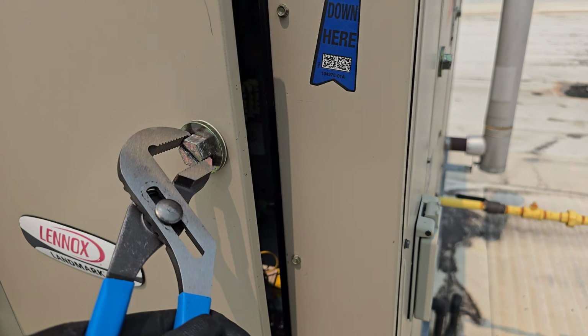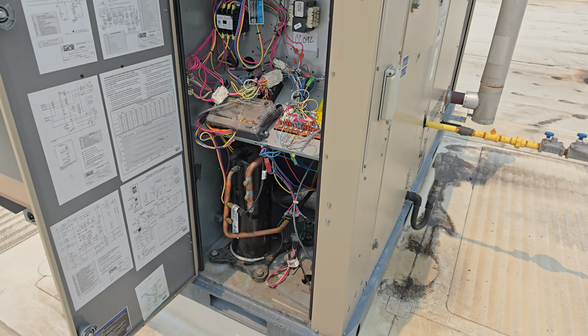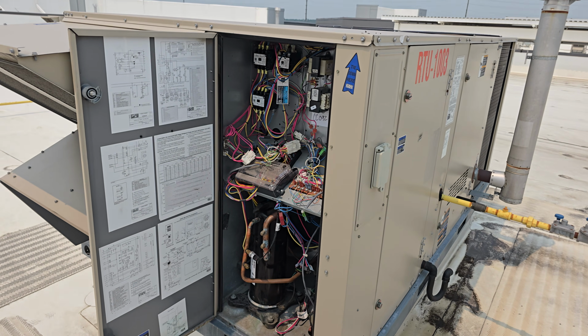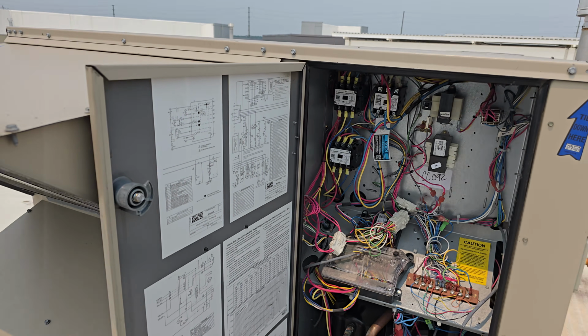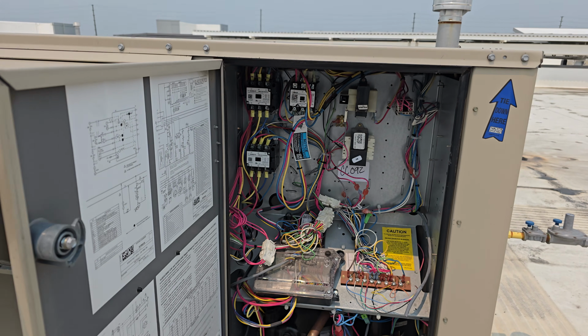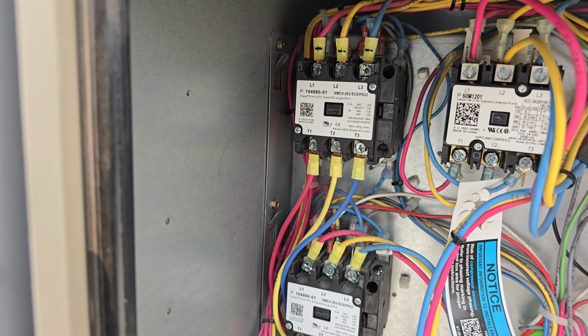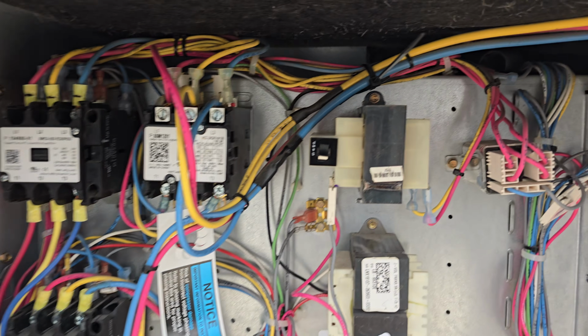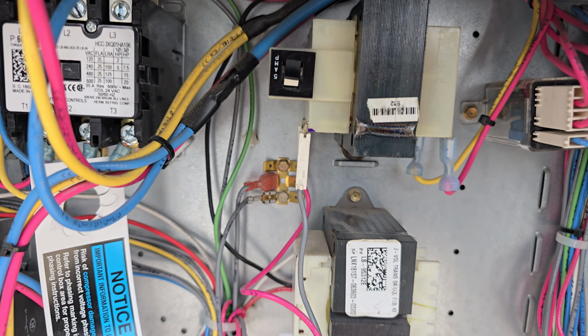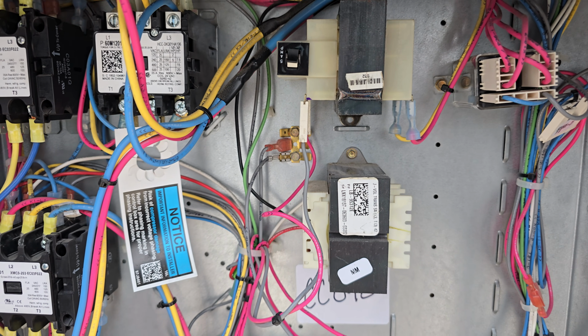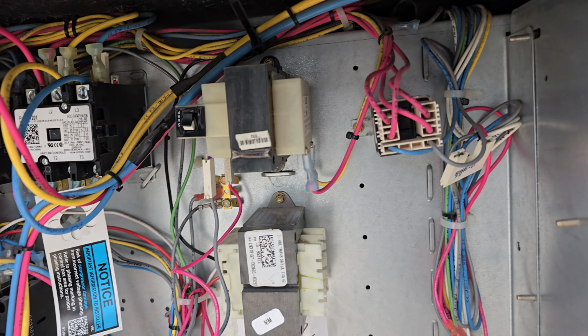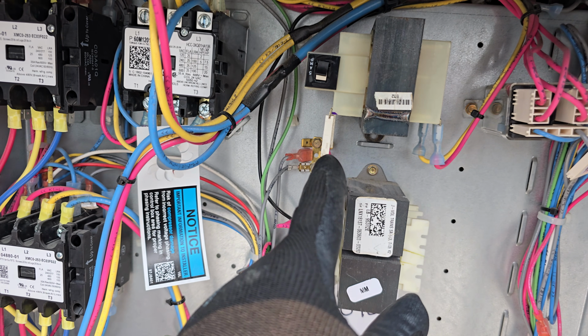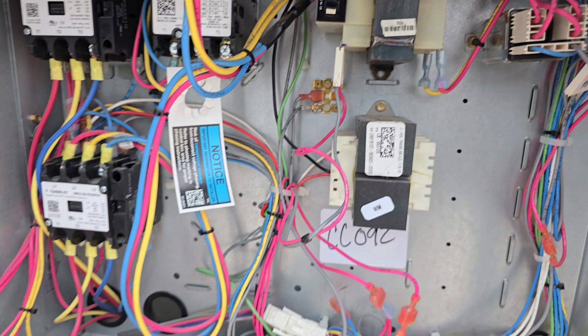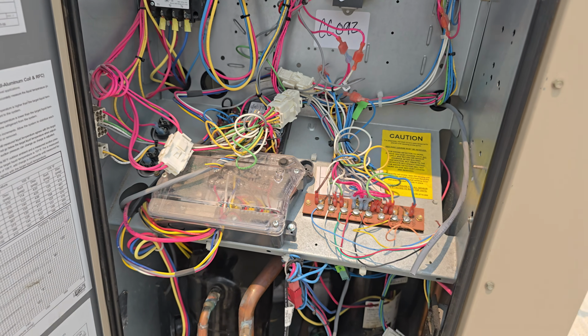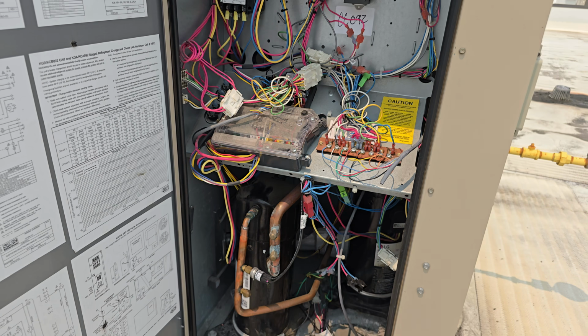Because the problem was not from the high side, and I have my power coming in, I'm going to check if my voltage is coming in here. Wow, okay, right away I noticed that the 24 volt tripped off. You can see this is 600 volt stepping down to 24 volt, and this is the 24 volt supplying all the 24 volt components.